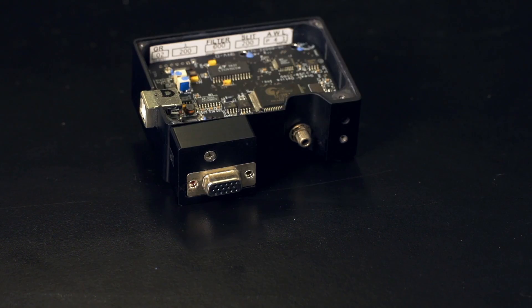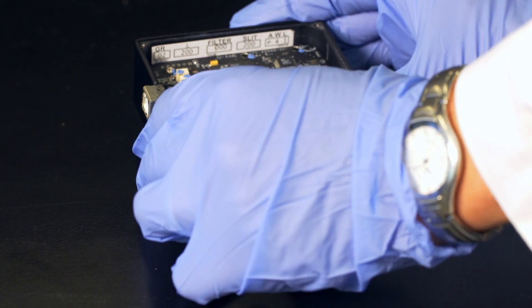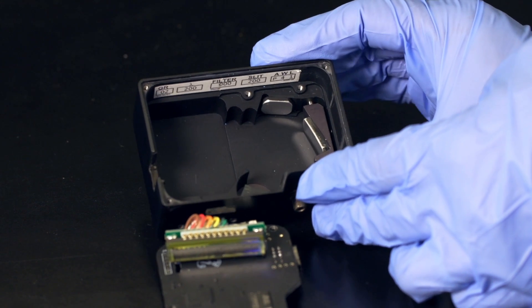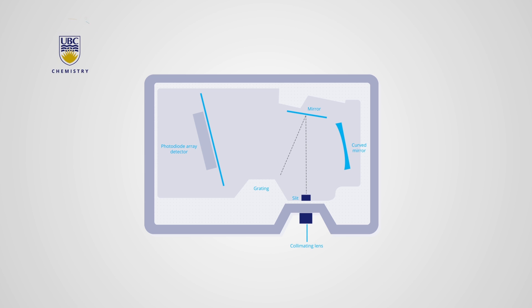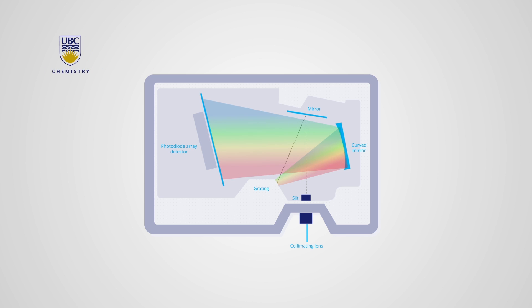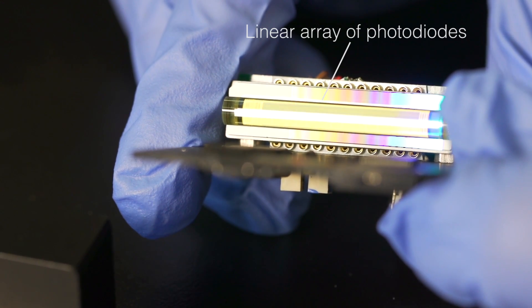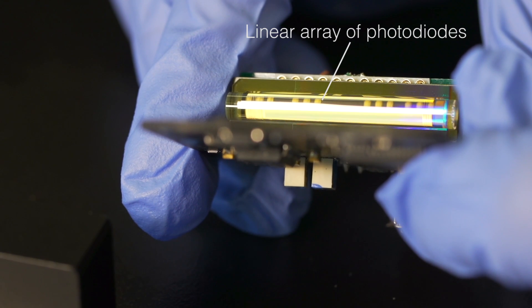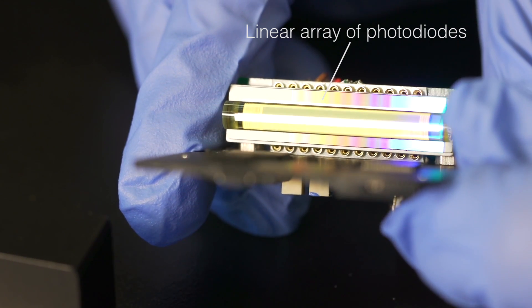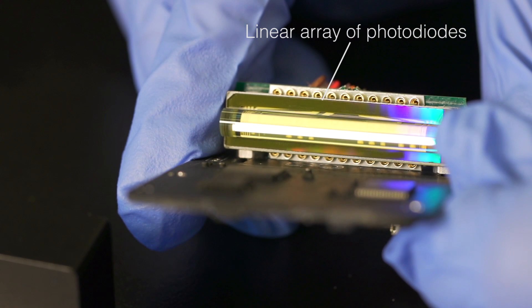This is what the inside of the spectrometer looks like. The light beam enters through a slit, then makes its way to the collimating mirror where it is made into parallel beams. The grating disperses the light beam into component wavelengths and directs it onto a mirror. The dispersed light is reflected over to the detector, which is a charge coupled device, or CCD, comprised of multiple photodiodes arranged in a long strip. The detector collects the light and converts the optical signal into a digital electronic signal.